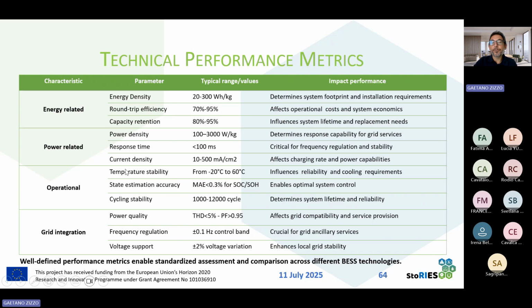Operational: temperature stability, because when the battery provides a service, temperature stability must be ensured, state estimation accuracy, and cycling stability. And we have seen how Terna has investigated the variation in lifetime of each battery with those experiments done in the two power intensive installations in Sicily and in Sardinia. And then grid integration technical performance metrics that are power quality, frequency regulation, and voltage support.